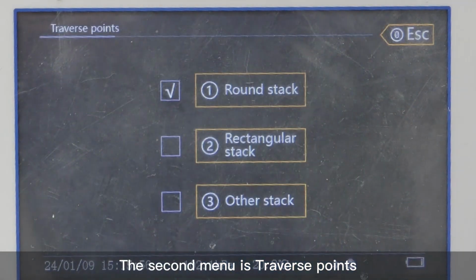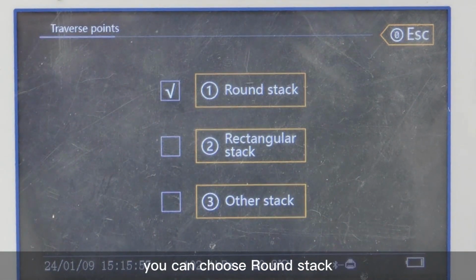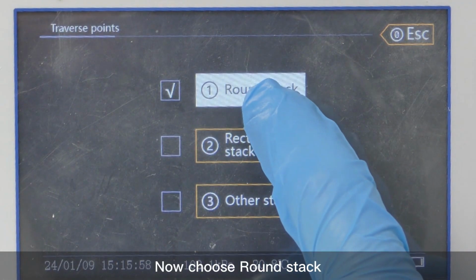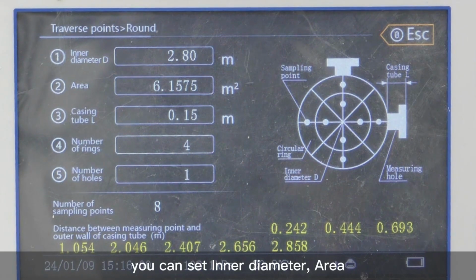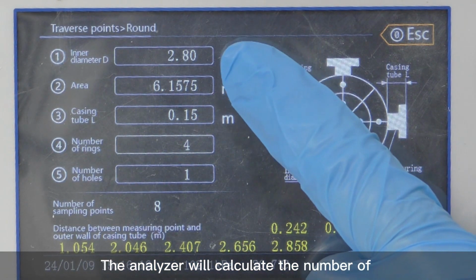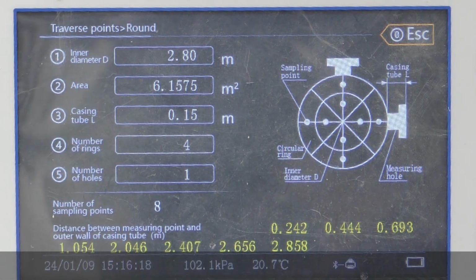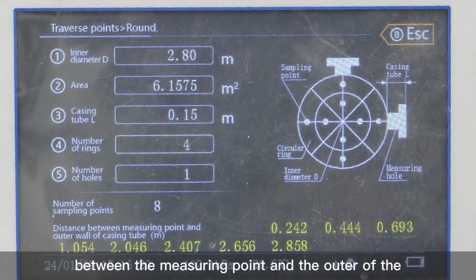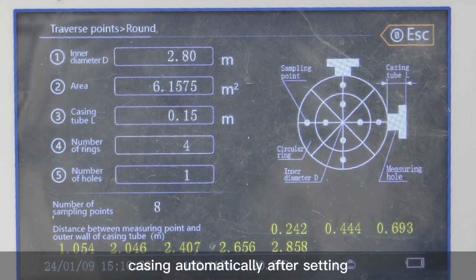The second menu is traverse points. You can choose round stack, rectangular stack or other. Now choose round stack. You can set inner diameter, area, casing L, number of rings and holes. The analyzer will calculate the number of sampling points and the distance between the measuring point and the outer of the casing automatically after setting.